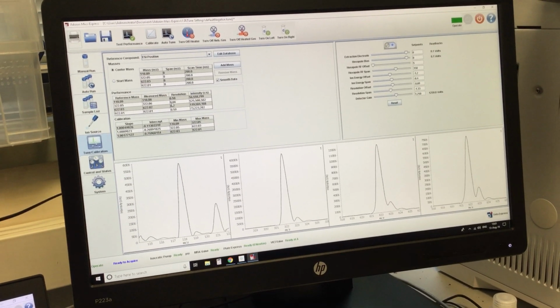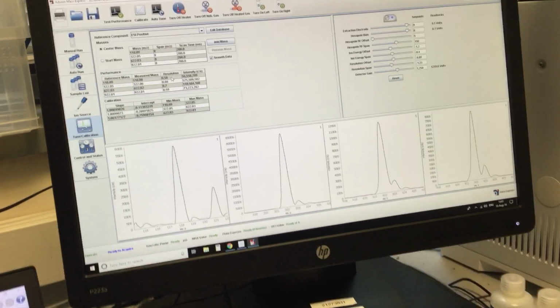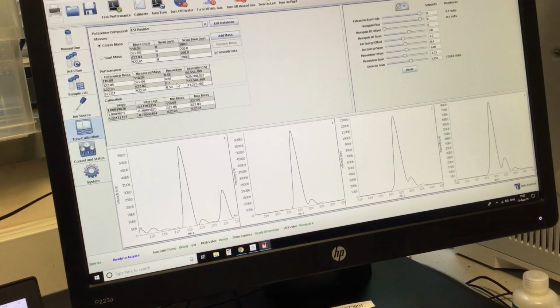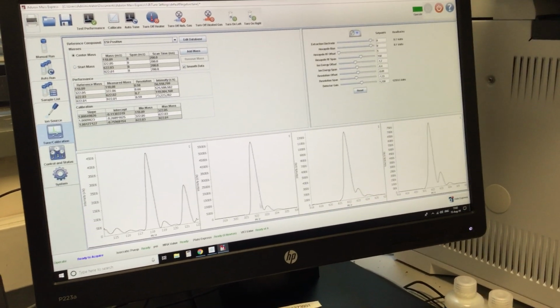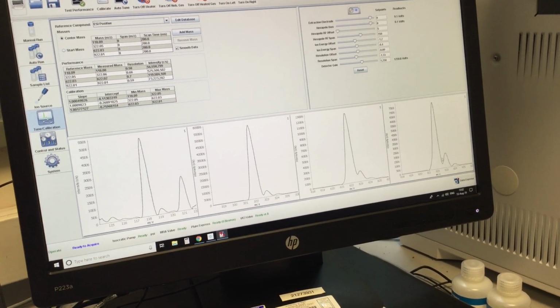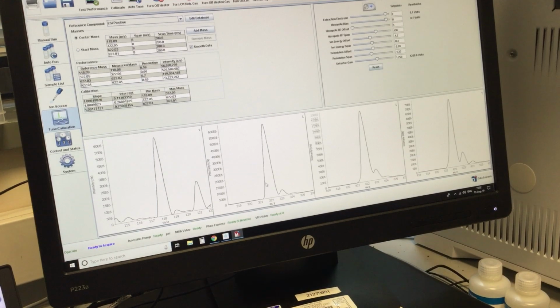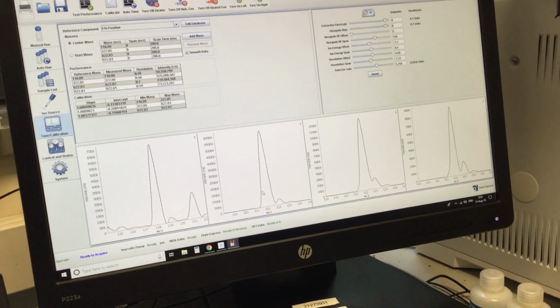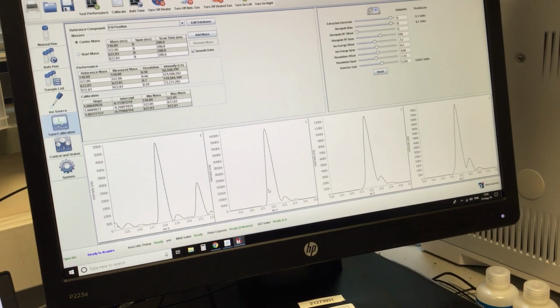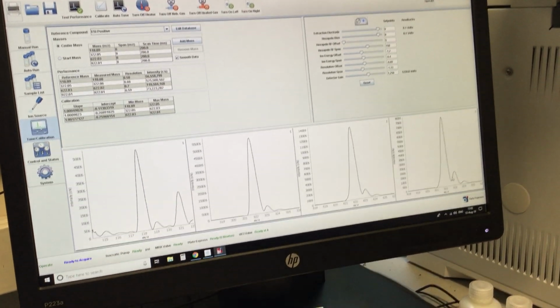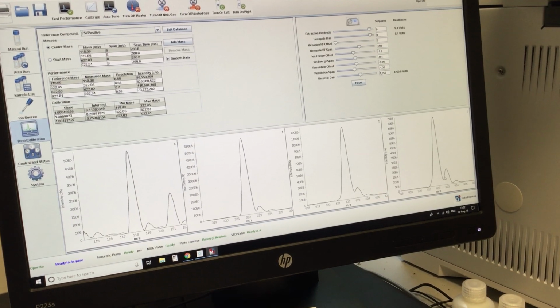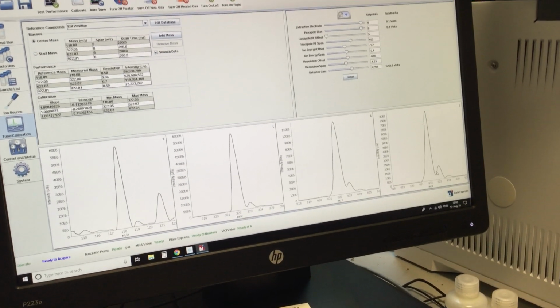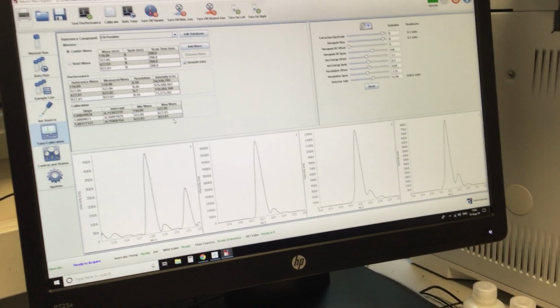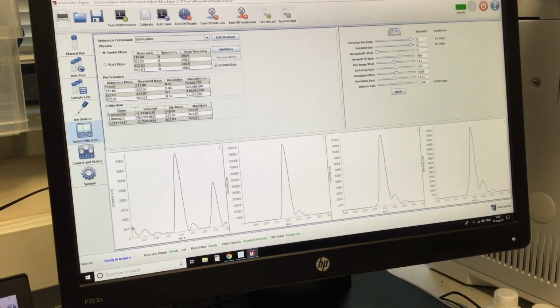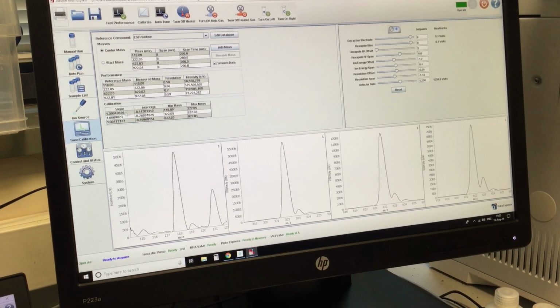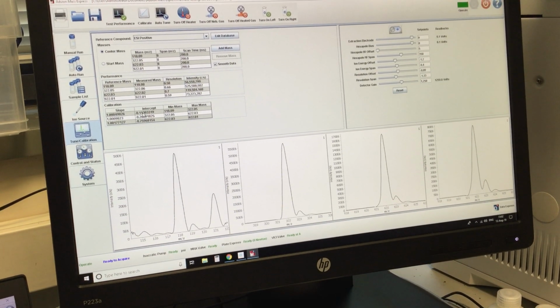Yeah. Okay. The resolution we're trying to aim for is between 0.5 and 0.7, and that's referring to the width of the peak. So you can see the isotopes, which is what you want, because that's going to help you identify compounds such as chlorine and bromine that have very unique isotope patterns. Yeah. So you definitely want that sort of resolution. As resolution goes down, intensity goes up, and vice versa.